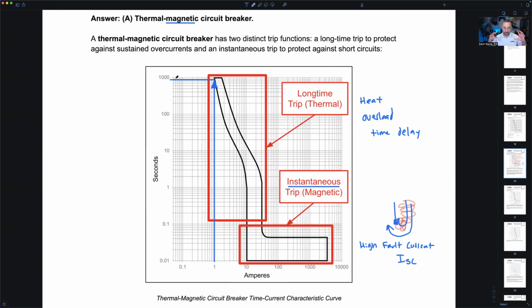So the hotter physically that this thing gets, it's like if I covered up a motor with a thick, heavy blanket, right? It's not going to have efficient cooling. That actually makes the current it draws increase. And it's like a runaway effect. The hotter thermally it gets, the more current it draws. So we want to protect it from those conditions by opening a breaker.